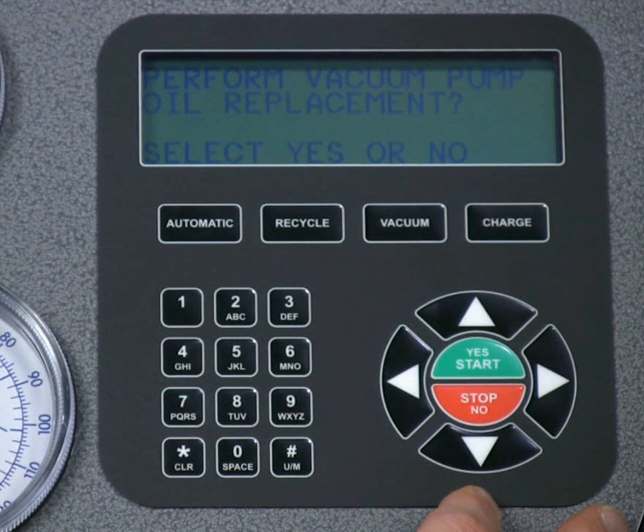Next up is vacuum pump oil change. As discussed throughout this video, oil must be periodically changed in the vacuum pump to ensure proper performance. If your machine is taking longer to pull a vacuum, your vacuum pump oil probably needs replacement. Also, if the oil is dirty or looks milky in appearance, replace it immediately.